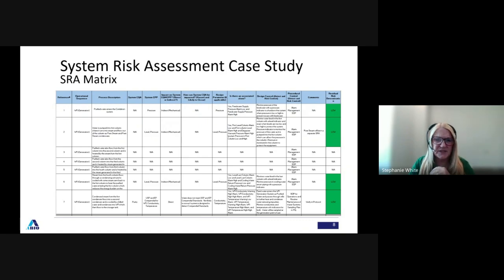I think number 6 was a level indicator and pressure we needed to monitor, since WFI is generated in stills, and we needed pressure relief valves and alarms in case pressure went too high, because this is a hot loop and pressures can build. So there's a bit of safety included, almost like a catch-all document for your critical components, critical alarms, and elements that could be safety factors.